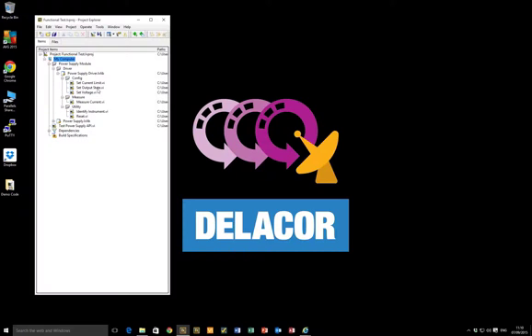So these are just members of that library, and these will typically be the VIs that write SCPI commands either via serial or via GPIB to an actual box type instrument that we might have sat on our bench. And typical of a power supply, the things that we might want to do: set the current limit, set the output state, set a voltage level, measure the drawn current, identify the instrument, or reset the instrument. So these are the low-level driver calls that we want to make.